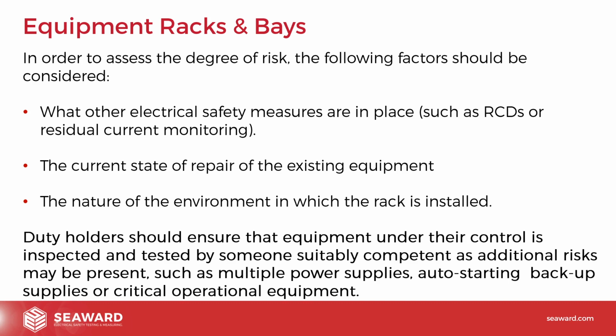What other electrical measures are in place, such as RCDs or residual current monitoring, the current state of repair of the existing equipment, and the nature of the environment in which the rack is installed. Duty holders should ensure that equipment under their control is inspected and tested by someone suitably competent, as additional risks may be present, such as multiple power supplies, auto-starting backup supplies, or critical operational equipment.